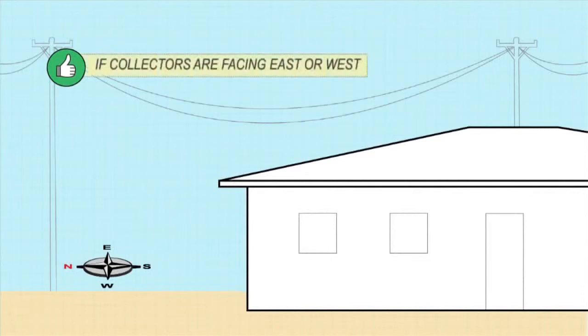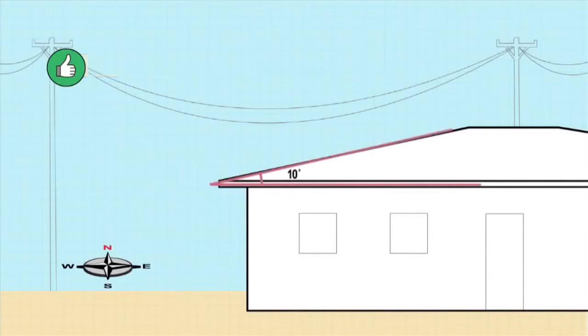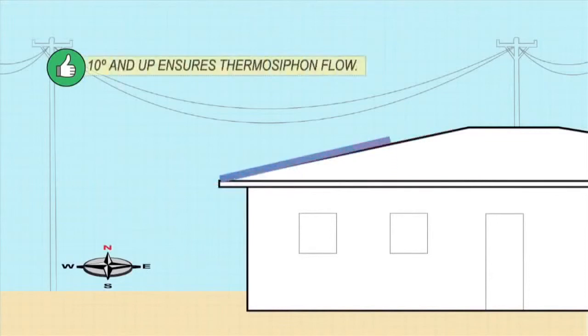If your collectors face due east or west, the lower the angle of inclination, the better. However, to allow thermosiphon flow, you must always keep the angle above 10 degrees.